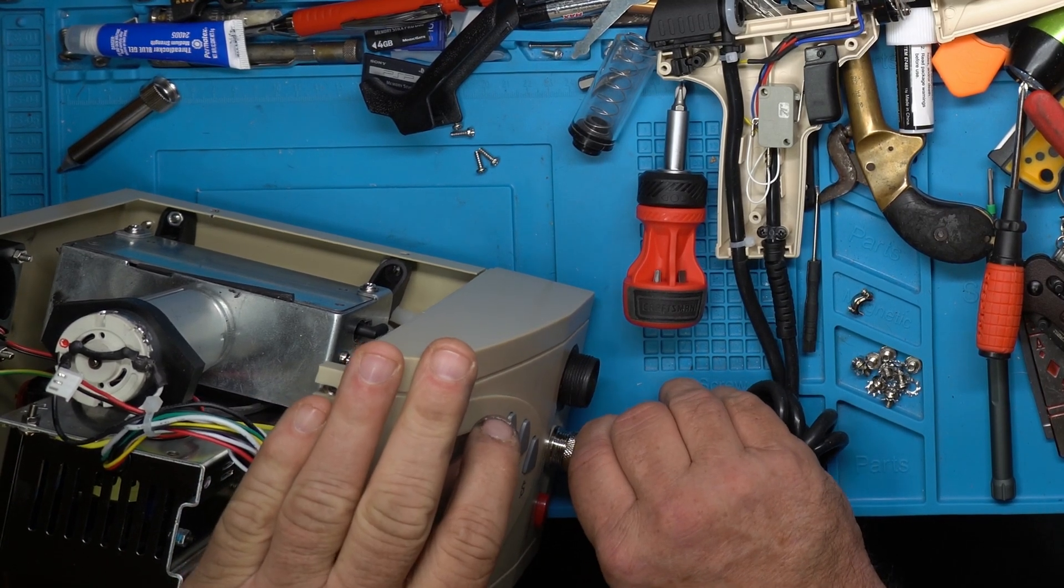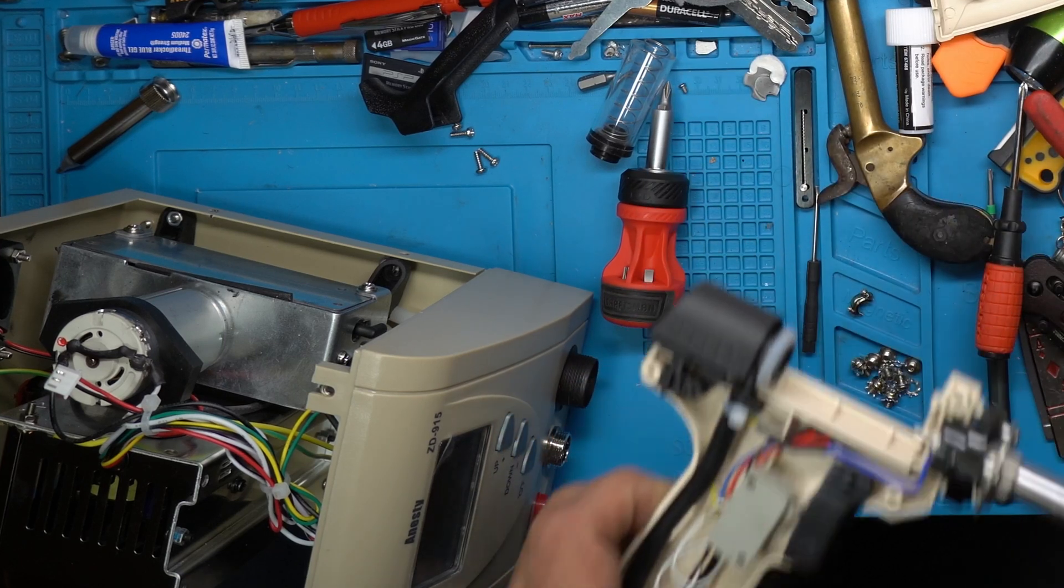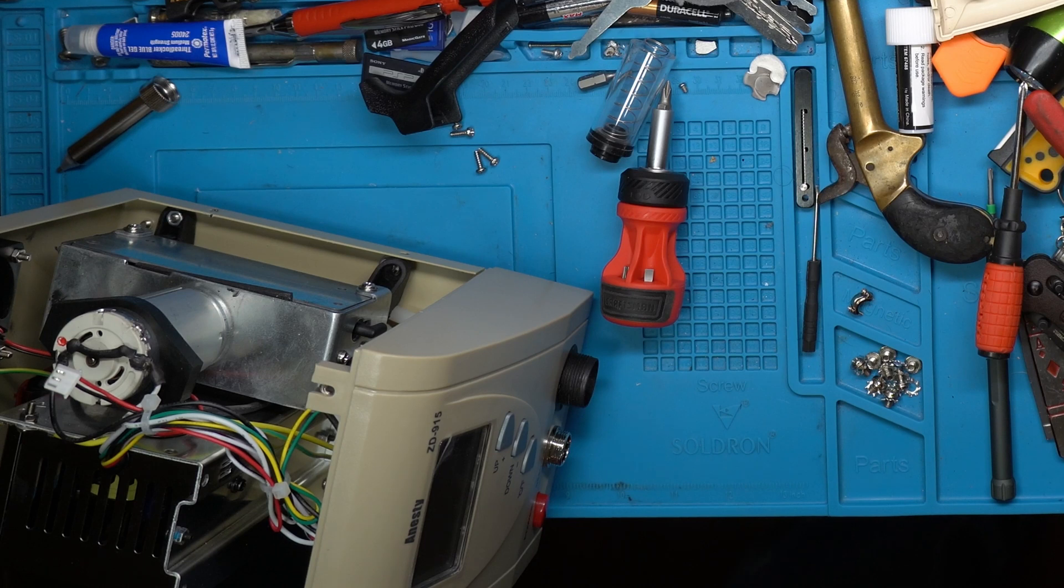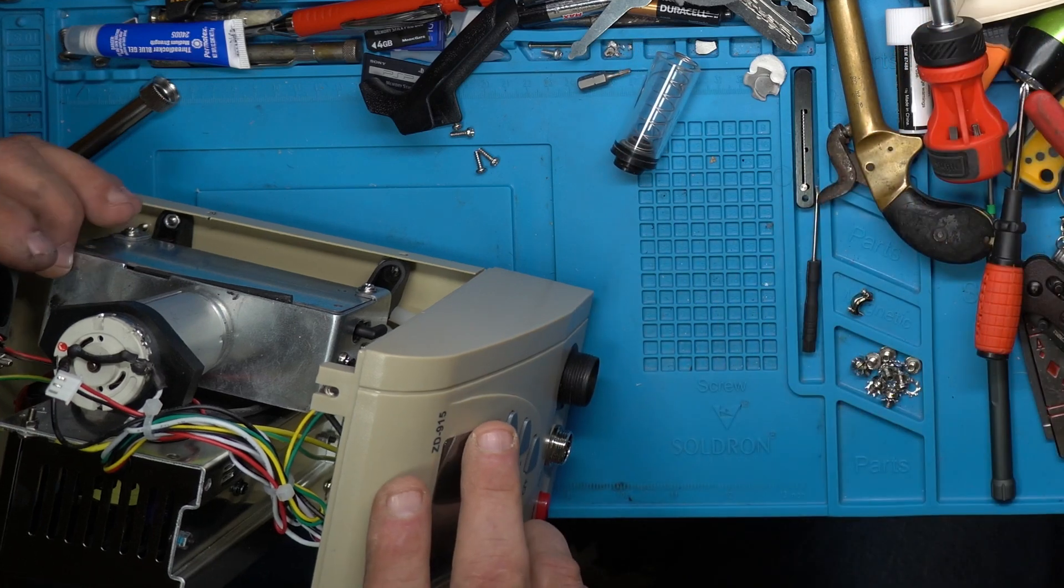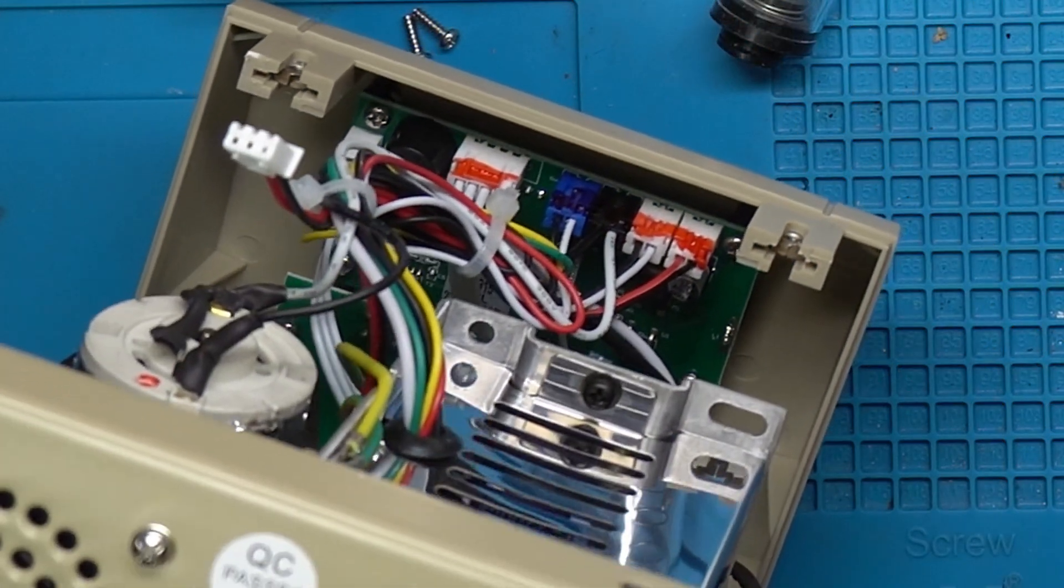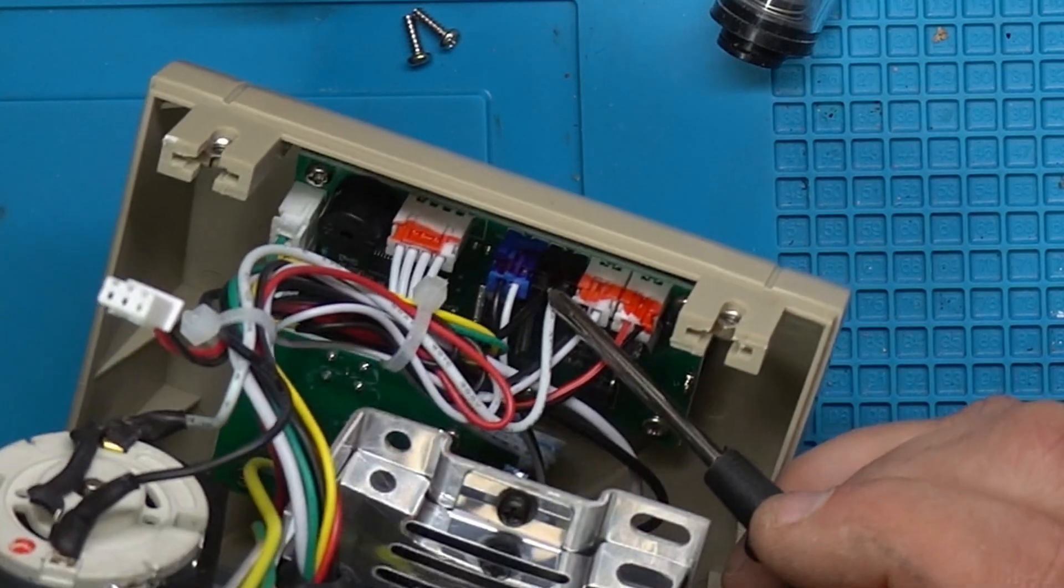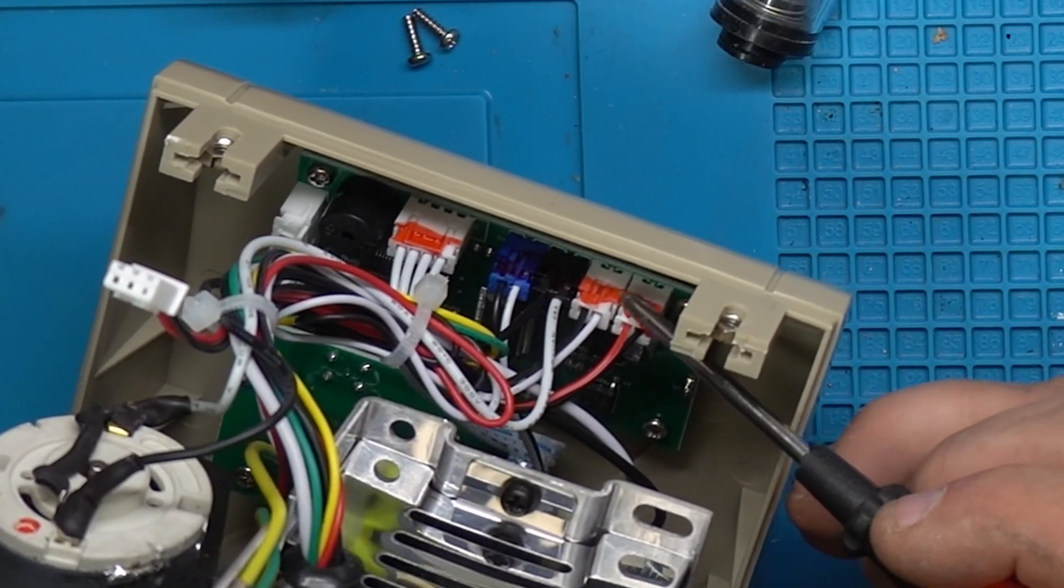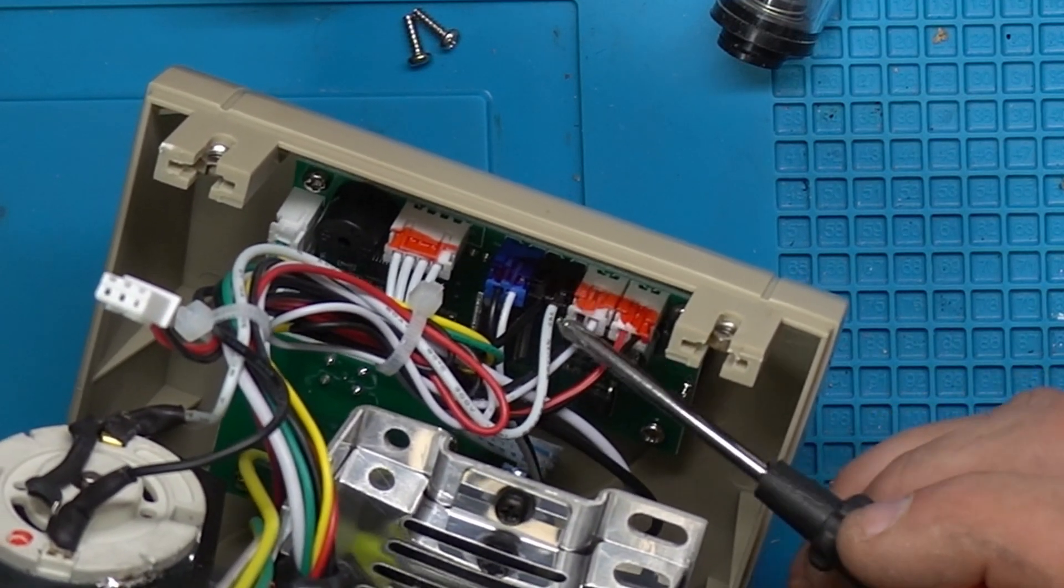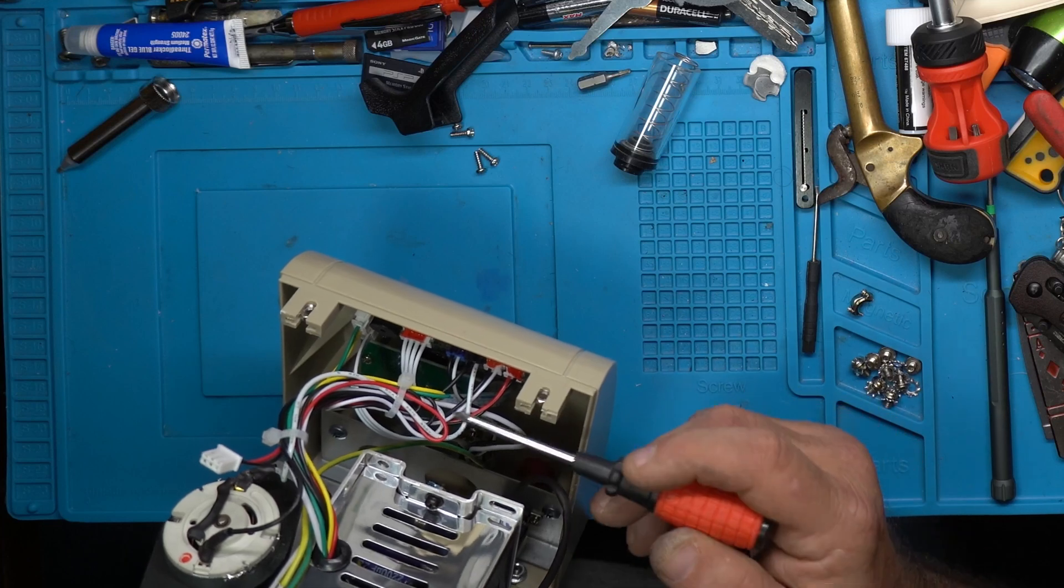So it's now a working unit. Let me show you exactly what the case was. Chances are, I mean I'm going to have to assume that this machine came from overseas and just being jostled around, although it was glued. I'm going to have to try to zoom in on this. If you look right here, this black one, see? Can you see it? You can see this little, very not very good glue job. This black one had come loose and of course that was supplying the 24 volts to go down to the handle and to return back.